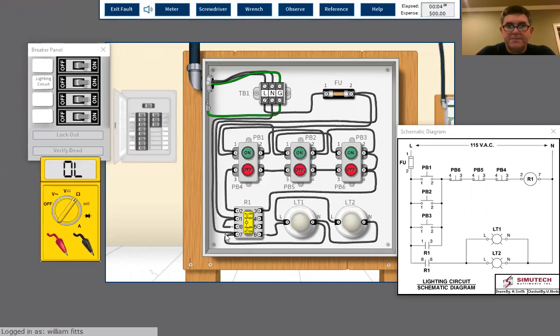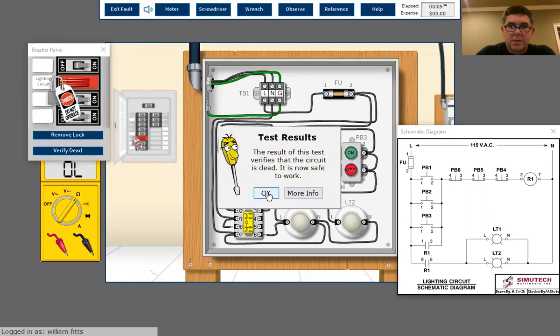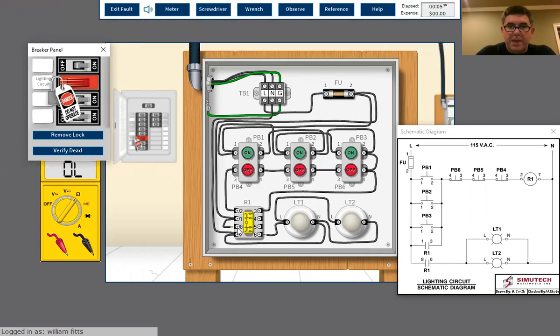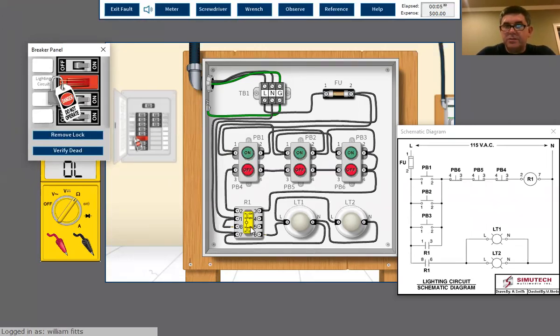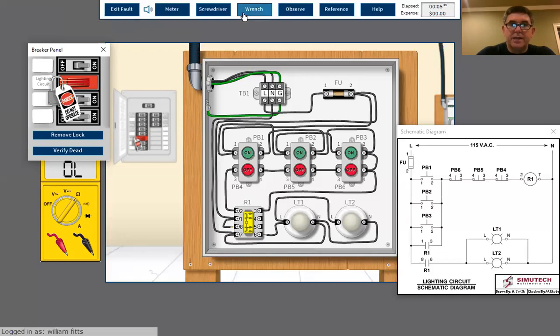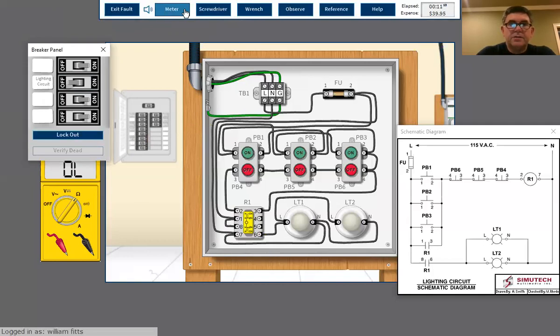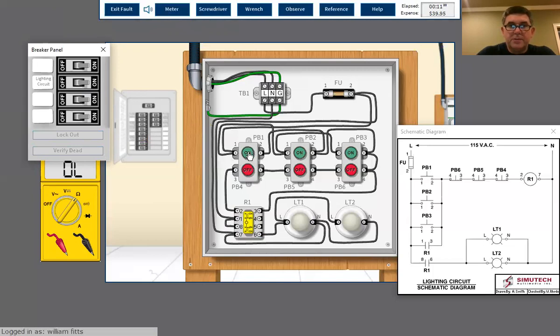Okay, never mind. Let's just stop there and go back to lockout. To me, that contact's bad, and I don't know any other way to check it other than to force that contact closed. A lot of times you can actually disconnect your wiring, put a meter across it and check that resistance, but we're gonna say it's bad. Let's connect everything back up. We know the fuses were good and all that, so let's see what happens. Well, that was it.